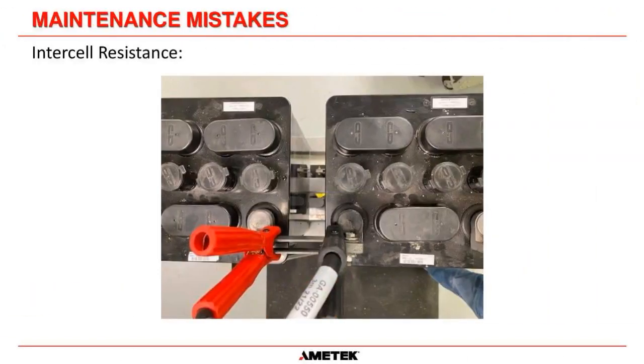It sounds easy, but what tends to happen - and this is a very good example of what people do - is they use the clamps from the Cellcorder or whichever device you are using, and clamp like this. The clamps are actually touching this bus bar here and this bus bar here, and this clamp is touching this bus bar here and that bus bar there. So the only measurement you're making is between this point and this point - you are not measuring the connection resistance here, and you can't see it because of the clamp.